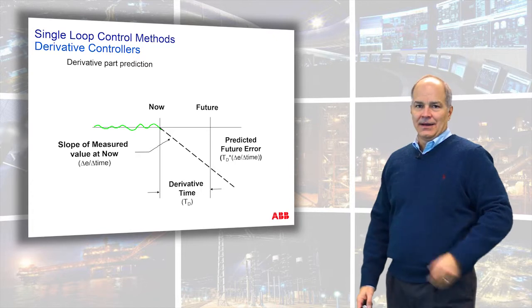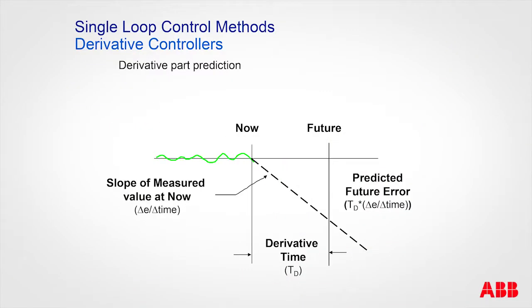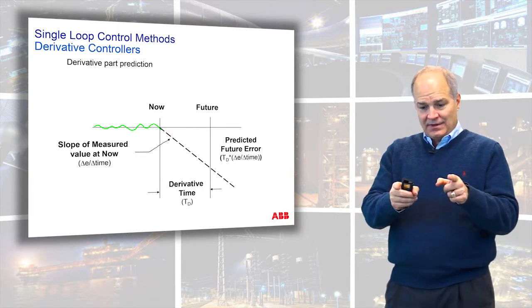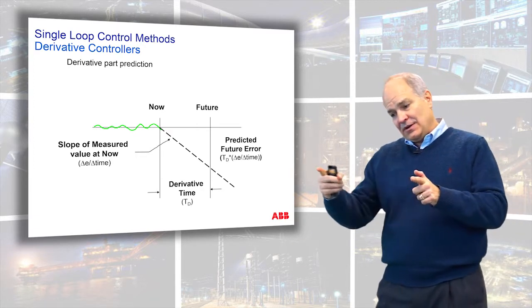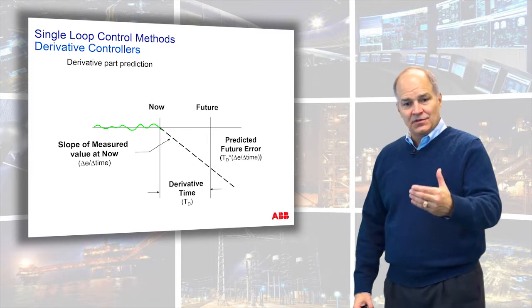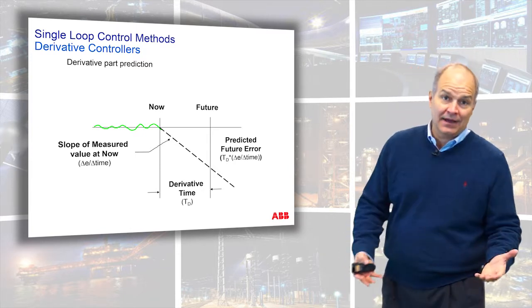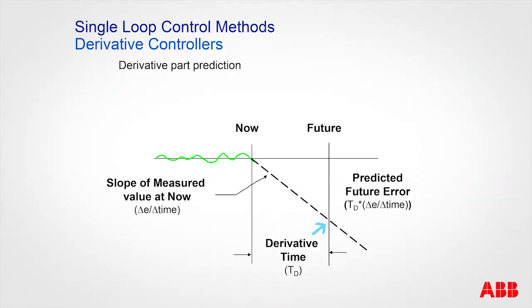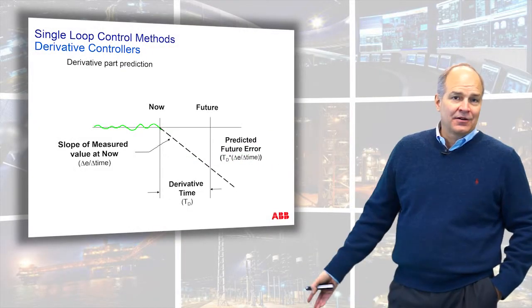This picture illustrates what we're talking about: 'now' is the current time, and based on the last two samples a slope is calculated — that's the derivative. You extend that slope out into the future; the time you project forward is called the derivative time. It's asking: how far into the future is my prediction accurate? The future error is estimated based on past errors — but is that always an accurate prediction?